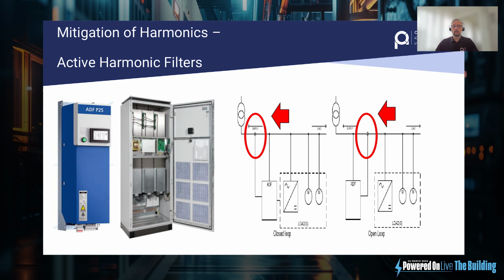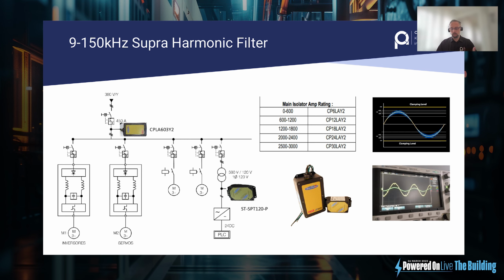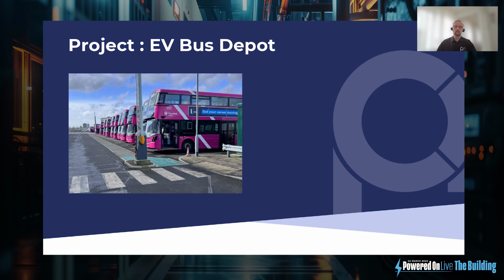So active harmonic filters is one way to get rid of the harmonic noise from EV chargers. We need to look at that holistically. Maybe it depends how big the EV chargers are. If it's a big bank of rapid chargers or if it's a small group in the car park, maybe they're not so critical and maybe the whole plant needs looking at rather than just the EV charger section. And the same with Supra Harmonics. So we have a range of things that can resolve those.